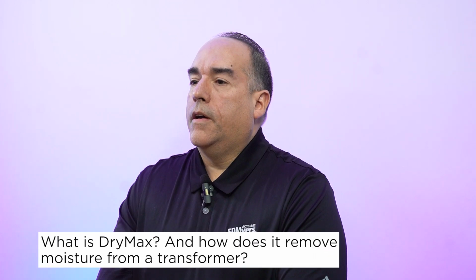What is DryMax and how does it remove moisture from a transformer? SDMyers has been manufacturing and selling DryMax systems for almost 2 decades. In order to improve the reliability of transformers by removing moisture, DryMax is an online passive transformer drying system that removes moisture while the transformer remains energized. That is very important. This system works over a longer period and therefore is able to remove moisture from both the oil and the paper insulation.